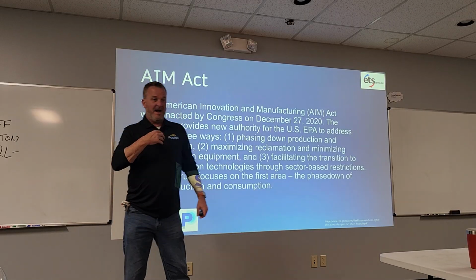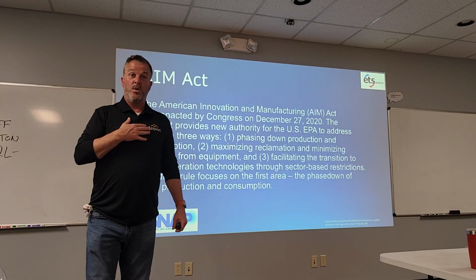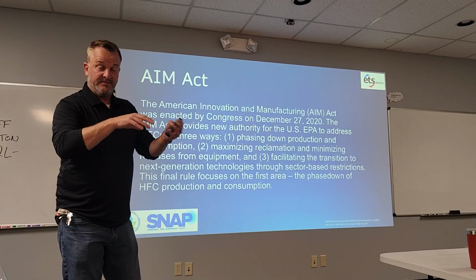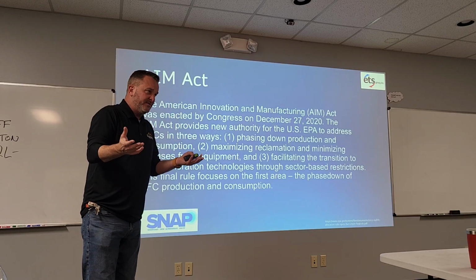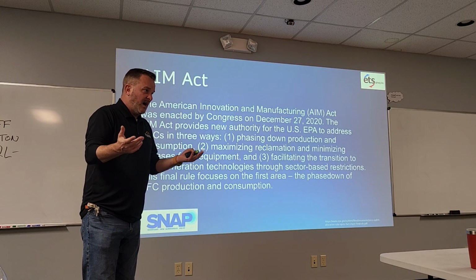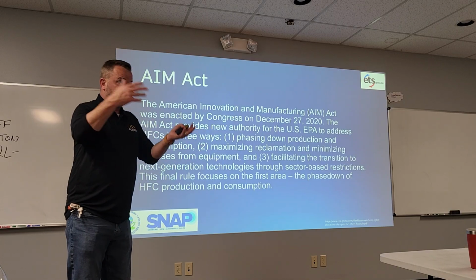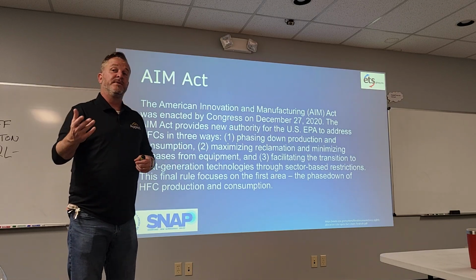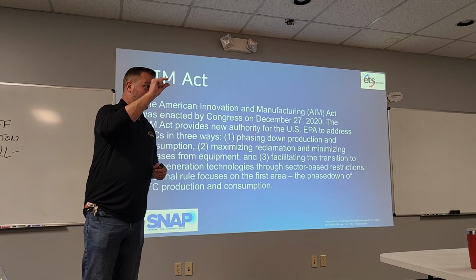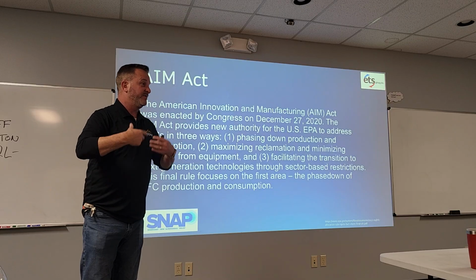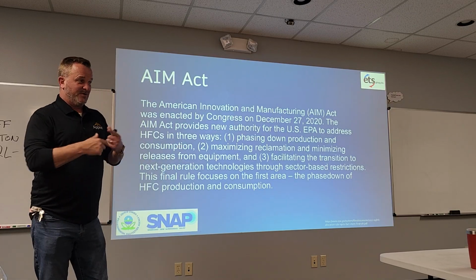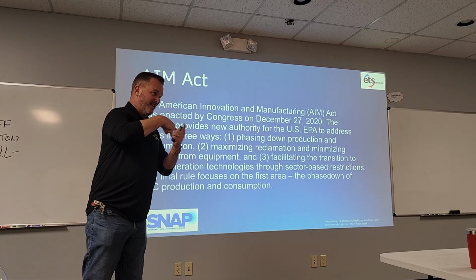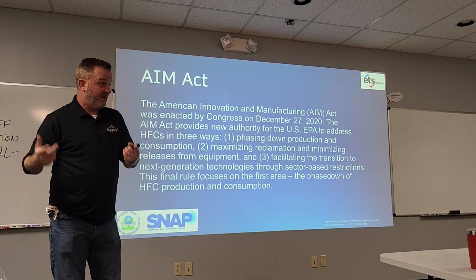Now here's my take on what was happening with a lot of leaky coils and everything else when we switched over to 410A. So what did coils used to be made of? Copper, right? And then they switched over to aluminum. And then with those aluminum coils, what did they start doing? They started making them thinner and thinner and thinner, right? Micro channels, so on and so forth. Well, again, with R22 systems, you didn't have that acid running on the inside. With 410A systems, you did.